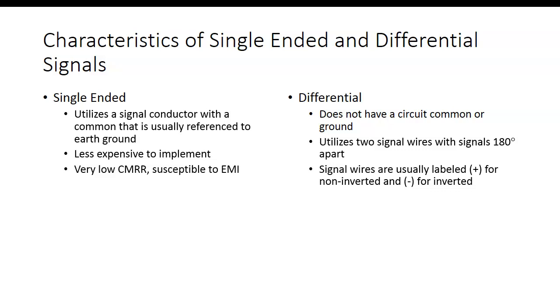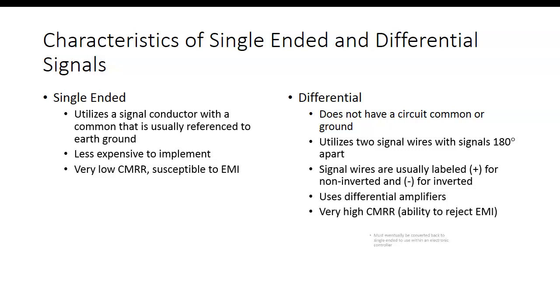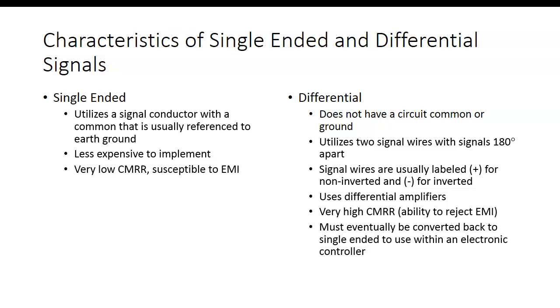But your PLC, inside your control system, it's all single-ended. So somehow we're going to have to go from differential back to single-ended. It uses differential amplifiers, has very high common mode rejection, ability to reject electromagnetic interference. It must be converted back to single-ended for use in electronic or even electrical control.